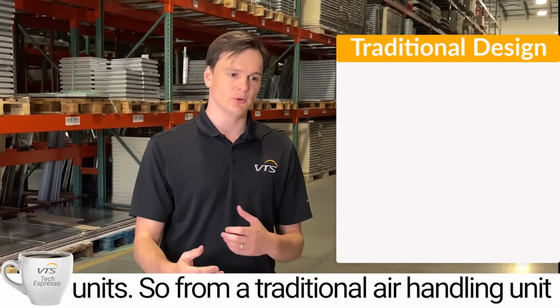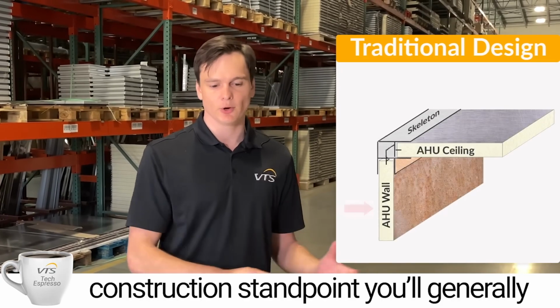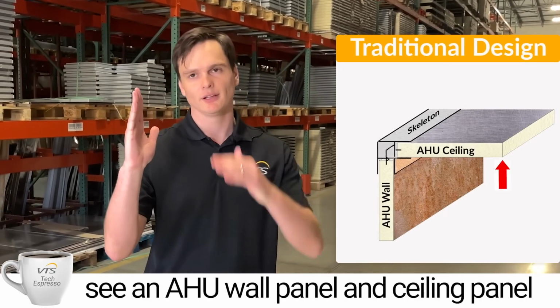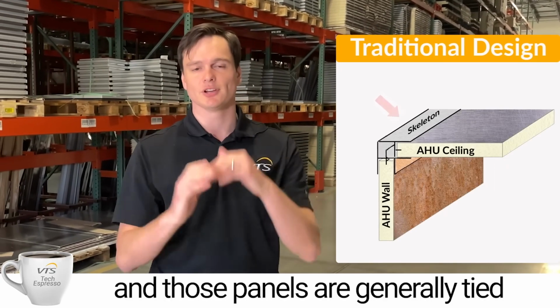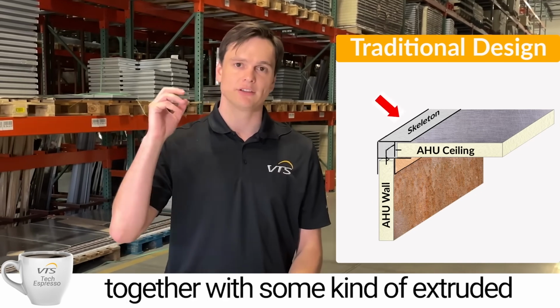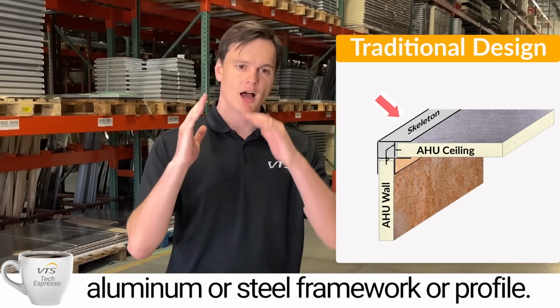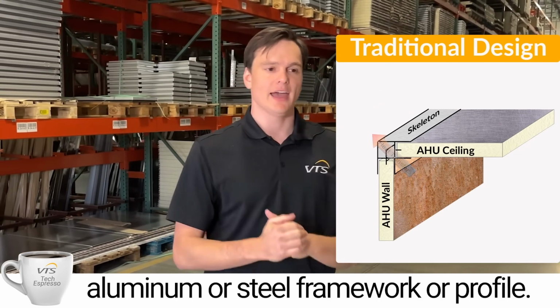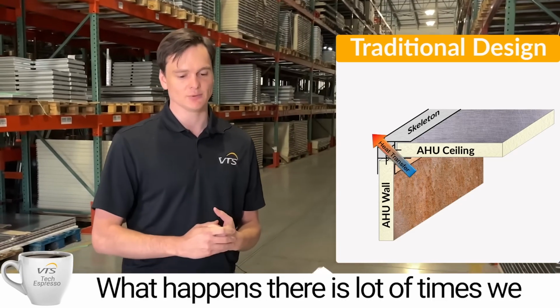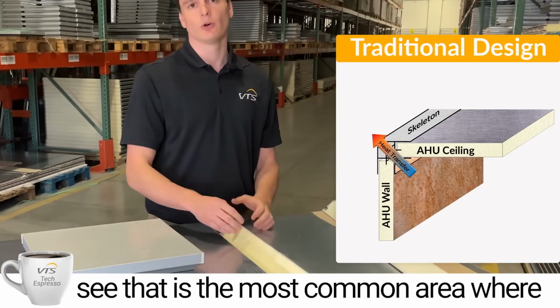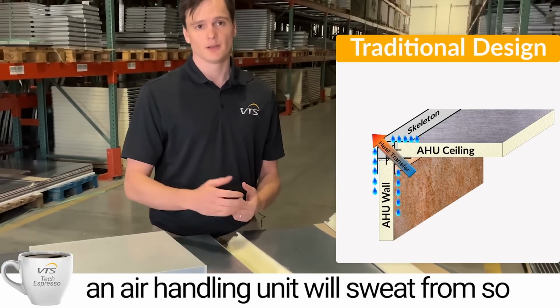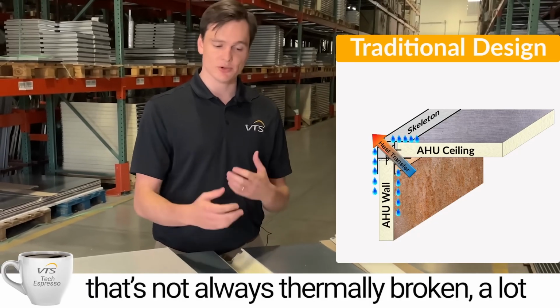So from a traditional air handling unit construction standpoint, you'll generally see a AHU wall panel and a ceiling panel, and those panels are generally going to be tied together with some kind of extruded aluminum or steel framework or profile. And what happens there is a lot of times we see that is the most common area where an air handling unit will sweat from. So that's not always thermally broken.